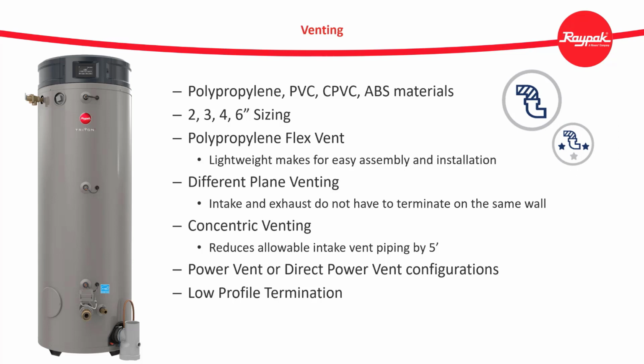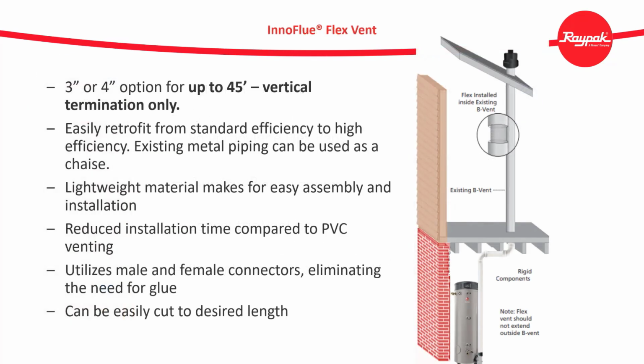The venting is highly adaptable as well. A wide variety of materials may be used, and you can even run the venting to a different plane than the air intake. Power vent or direct vent configurations can be built. If you choose to use InnoFlue Flex Vent, you can use the existing B vent as a chase. You can run up to 45 feet of the Flex Vent and then add 15 feet of rigid pipe down below to the unit. This will be minutes instead of hours of vent installation time.